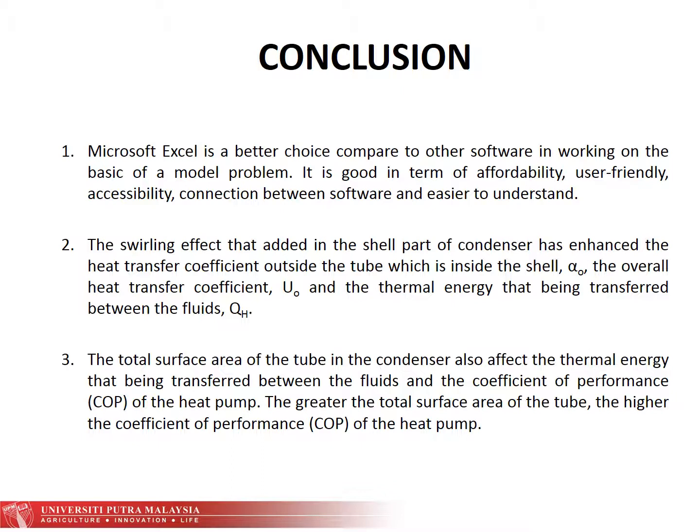Second, the swirling effect that is added in the shell part of the condenser has enhanced the heat transfer coefficient outside the tube, and the overall heat transfer coefficient as well as the thermal energy that is transferred between the fluids in the condenser. Last but not least, the total surface area of the tube in the condenser also affects the thermal energy that is transferred between the fluid and the COP of the heat pump. The greater the total surface area of the tube in the condenser, the higher the COP of the heat pump.